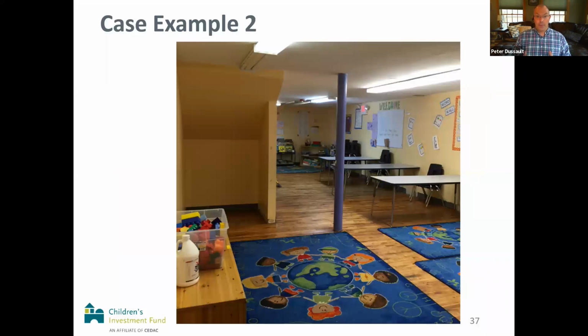Here's another example, and again I'll go through my decision process. I look, and I don't see any diffusers. This leads me to believe there's not an HVAC system serving the space. You may have baseboard heat, but that doesn't work because it doesn't provide airflow. In this case, I would recommend deploying a portable HEPA filter.